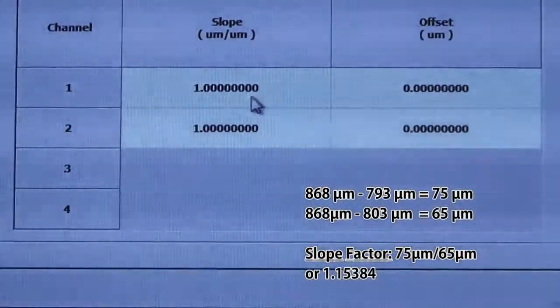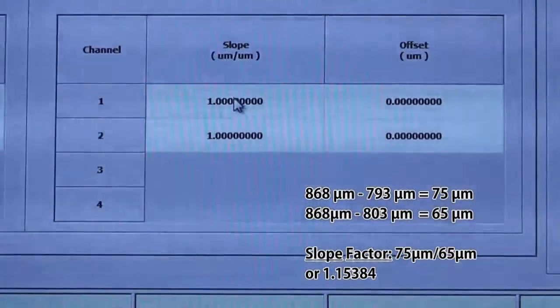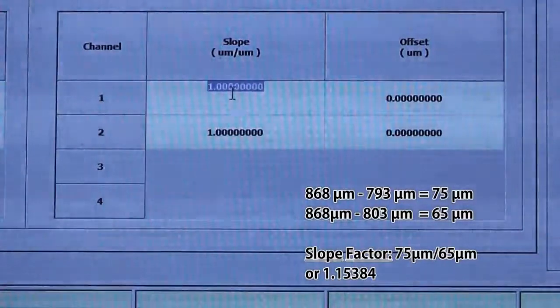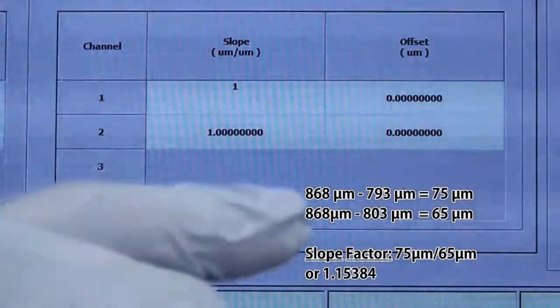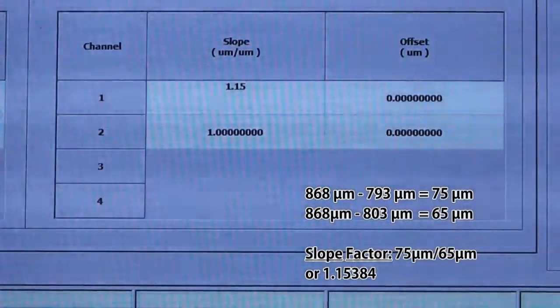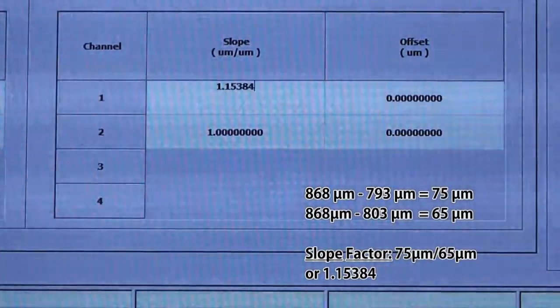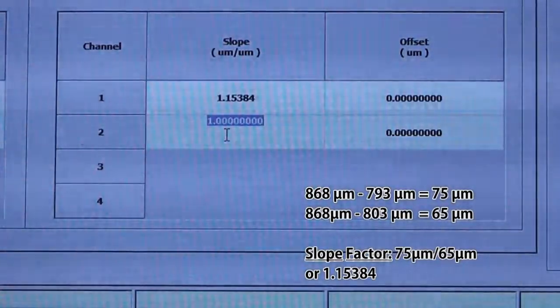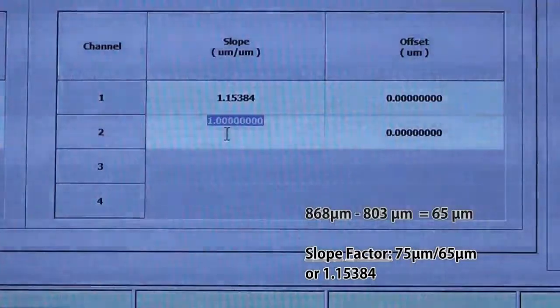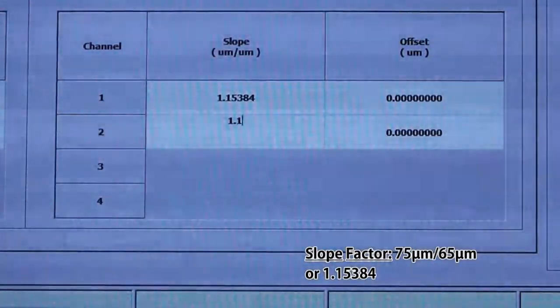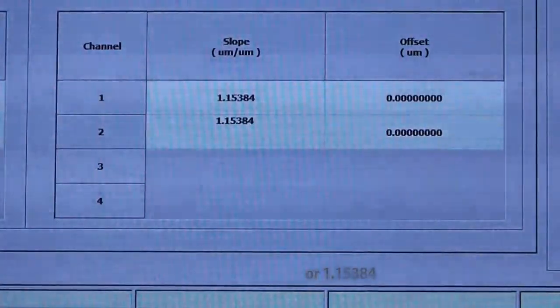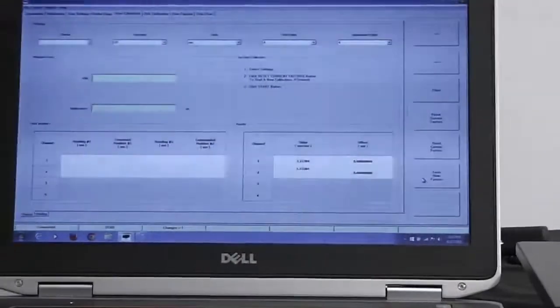What we're going to do is we're going to change these to the new slope factor. So what I do is I double click on this and I key in the sapphire slope factor, 1.15384. That's entered in the channel 1 and channel 2 for both probes, 1.15384. Once those are keyed in, we click on the save new factors button. So our new slope factor is now saved to the system.